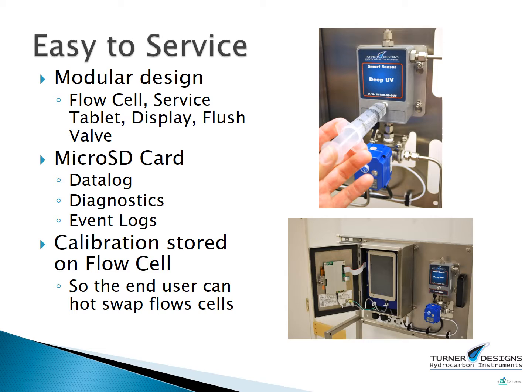The major components of the TD120 can be changed in the field without the instrument coming out of service. The flow cell and the flush valve both have quick disconnectors, while the tablet and the display are easy to change as well.